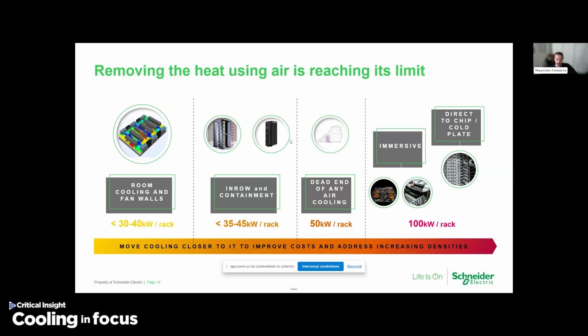However, the most recent ASHRAE recommendation, in particular the H1 envelope released by ASHRAE back in 2020, says that more than 50 kilowatts per rack requires a supply air temperature between 21 and 24 degrees C versus the usual 27 in the recommended envelope. This makes it possible to cool with air cooling, but completely inefficient. So it's a different angle we need to use. Despite the technology being able to do this, 50 kilowatts is the dead end of air.